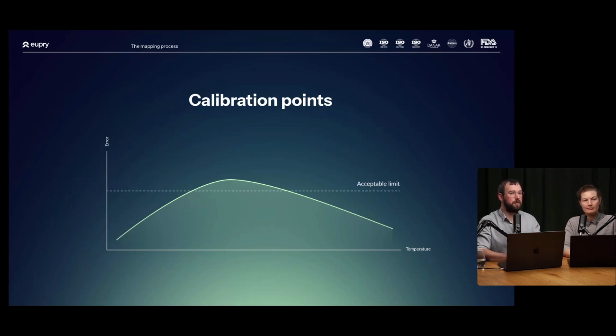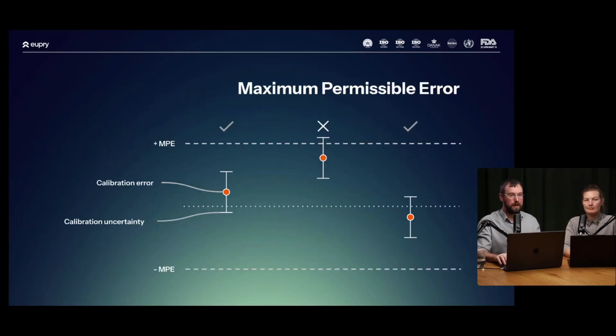Let's say we have an acceptable limit for how much error we're willing to accept in a calibration, and this goes here. Let's say that I choose 2 calibration points at the lower limit and at the upper limit. How do I know that in the middle of this interval, the error is not unacceptable? I simply do not know. And that is why you need a third calibration point. You can go on and on about the technical reasons, but it's basically because we know that temperature error tends to form as a second degree polynomial. And in order to catch that, you need 3 calibration points. And that's the reason why.